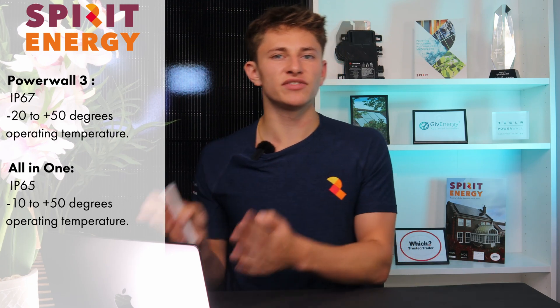Just to run through some quick technical specs. In terms of physical size, they're very similar, although the GivEnergy is a bit deeper. It's also much heavier at 173 kilos compared to the Powerwall 3, which is 130 kilos. Both units are rated to go indoors and outdoors, although Powerwall 3 is flood resistant up to 2 feet as a result of the body being laser welded. Powerwall 3 is IP67 and All-in-One is IP65. The All-in-One has an operating temperature of minus 10 to plus 50 degrees, whereas Powerwall 3 can operate from minus 20 to plus 50 degrees. Powerwall 3 also has active thermal management, which will pre-condition the battery to make it as efficient as possible in severe weather conditions.